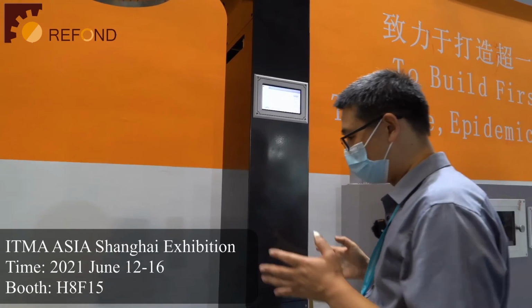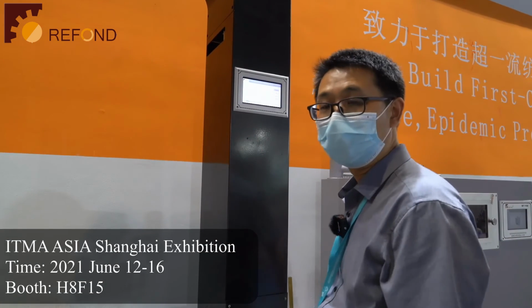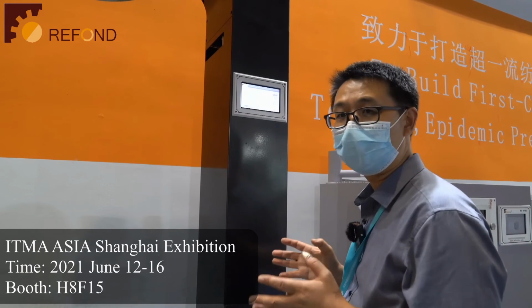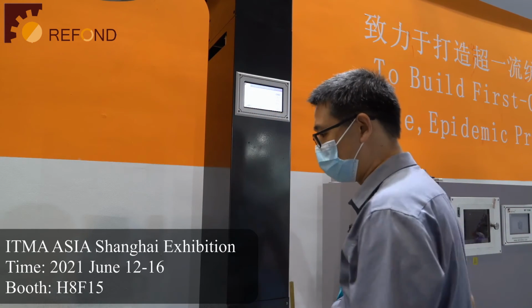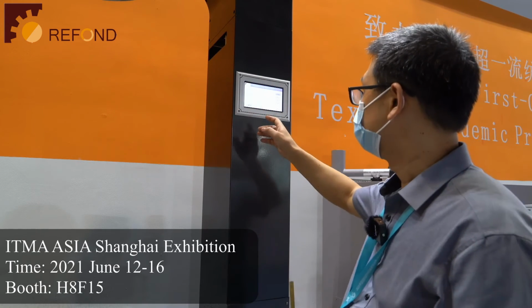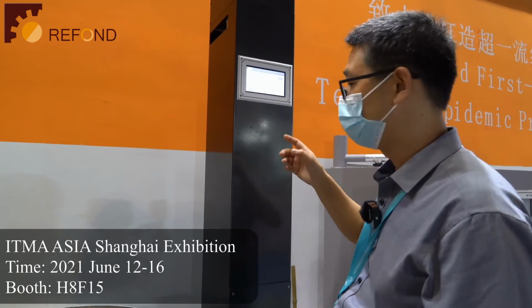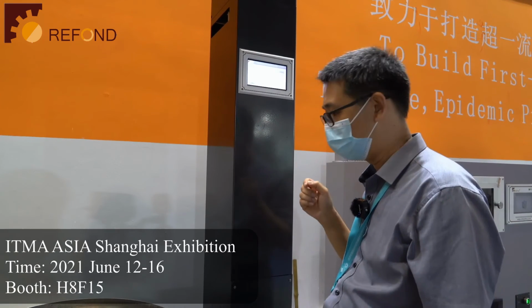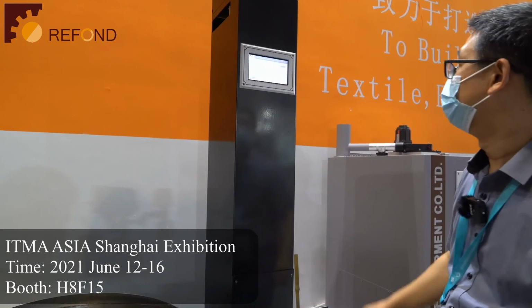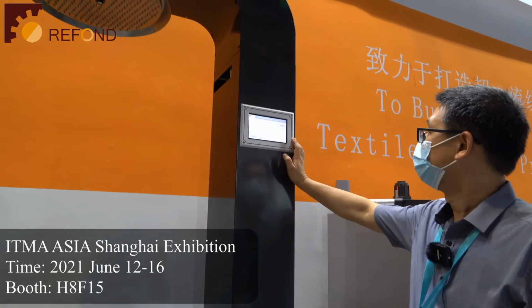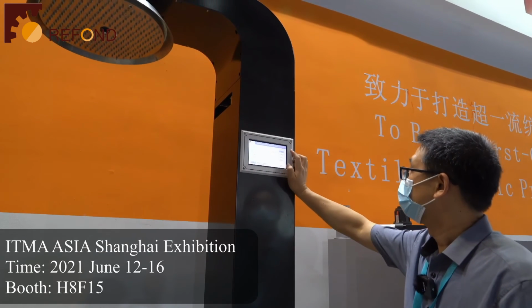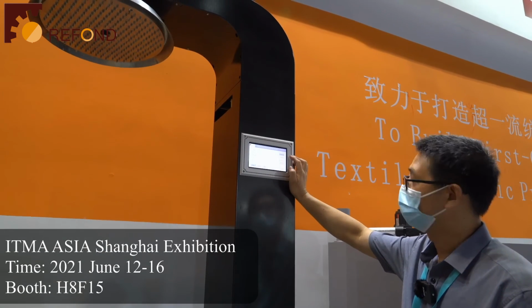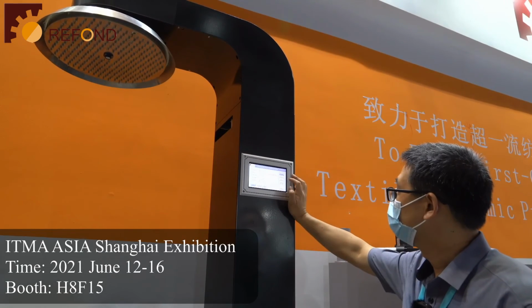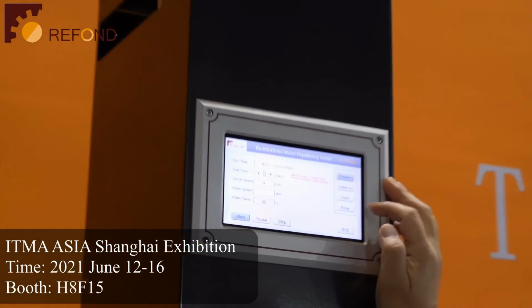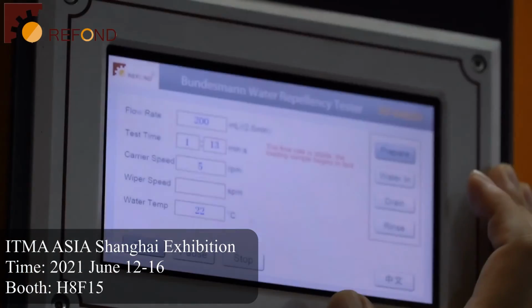If you stop the water drop every time, it will take a long time for the preparation of the test, because you need a long time for the machine to get a stable condition. The other function for this machine, you can manually control the water in and the drain, everything you can control.